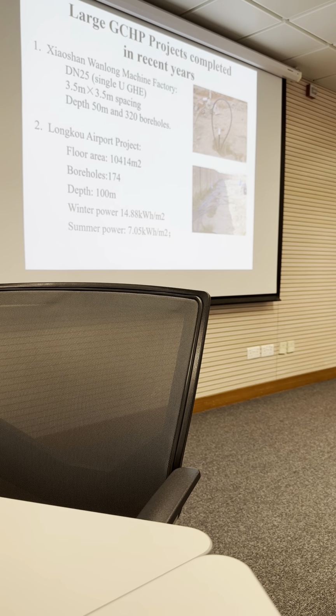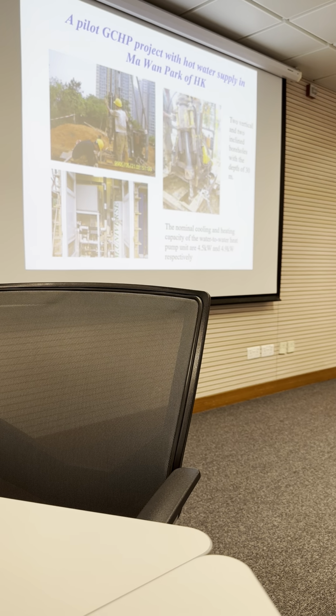So we installed a water-to-water heat pump system with a unit of 4.5 kilowatts for cooling and 4.9 kilowatts for heating. You may say, can we just use the system for cooling in summer or throughout the year? I must say it's not good, because if you inject too much energy into the ground, what happens? The temperature is higher and higher because not much water flows inside. Then heat energy is accumulated around that area. I'll show you later. You see, this is a ground coupled heat pump system.